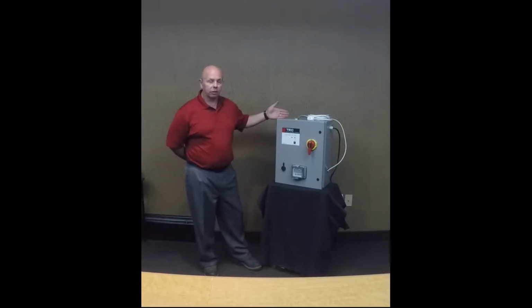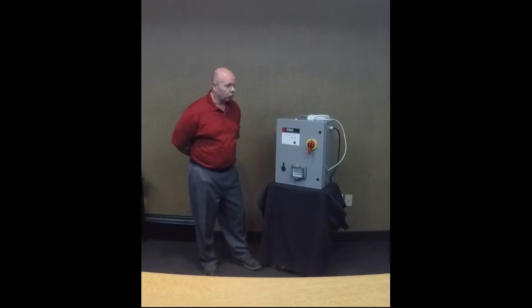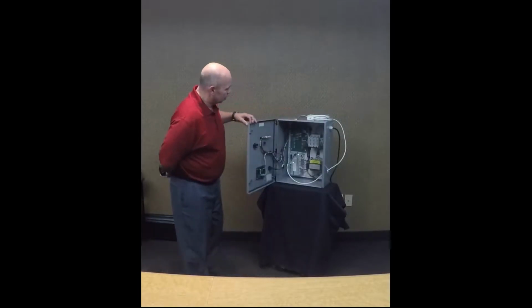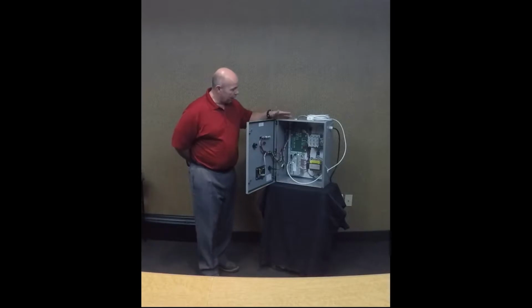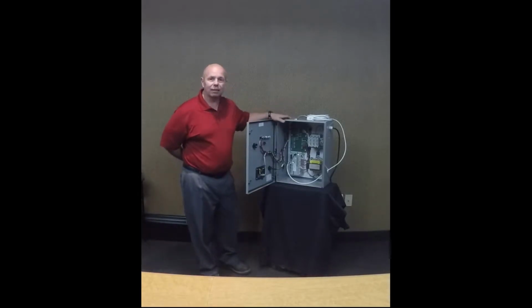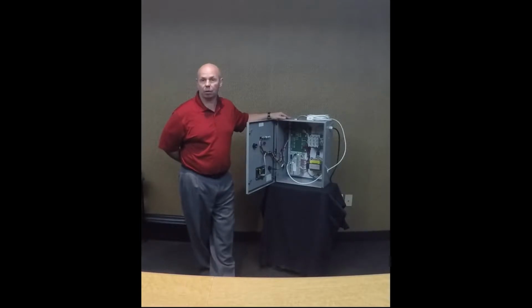The P1 arc flash relay system comes in a NEMA 4 enclosure, has an optional rotary disconnect as well as a convenience outlet. Inside, we see that the arc flash relay system has power, comes in through the rotary disconnect. This power that can be applied to power up our system can be between 120 volts up to 480 volts. It is configurable for any of the US voltages, so 120, 208, 240, 480 volts. The P1 arc flash relay system has a short circuit current rating of 200,000 amps. This has been verified through UL 508A supplemental SB methods.